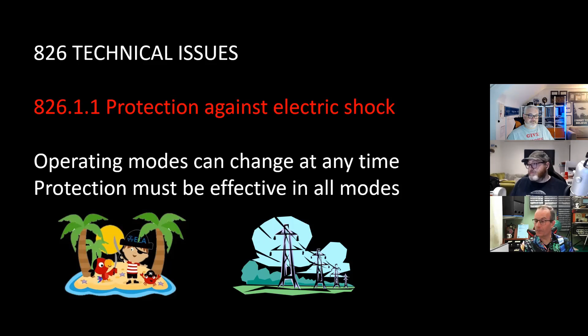Very good point. So whatever protection device you're putting in has got to work in every operating mode of your installation. And the idea is that it could and will, in fact, change. Again, it switches to a different supply source, with different fault characteristics. As a quick example, if you've got a grid supply, say TNCS, you're going to have typically very high fault current and very low earth fault impedance. However, once you go to island mode and you're supplying from batteries, it's not going to be a high fault current anymore. It's going to be very low, and the impedance is going to be considerably higher. So think about that. And then, of course, you have the situation where you're using multiple devices at the same time. Exactly. So anyway, we'll move on.